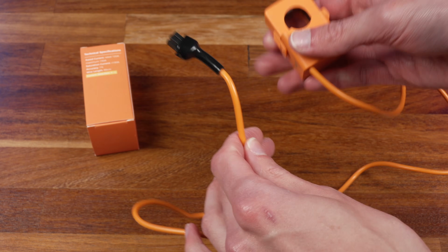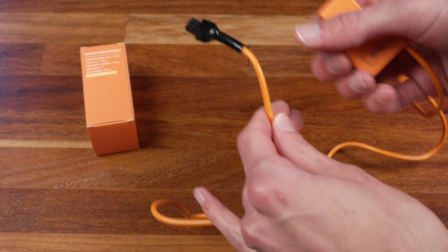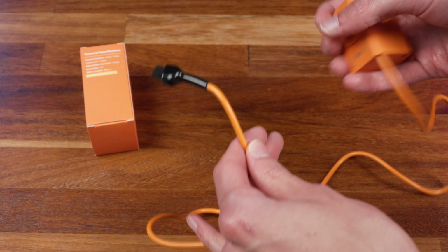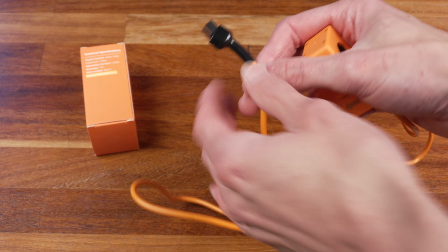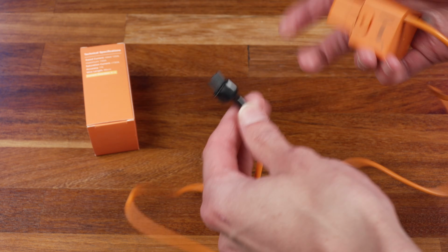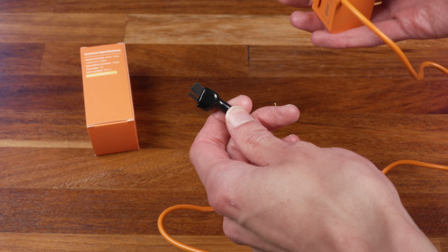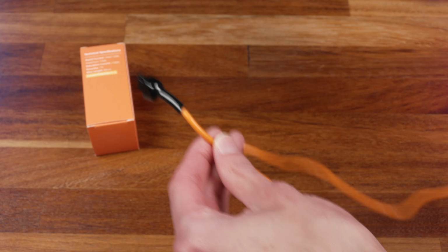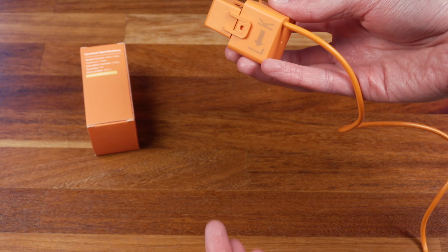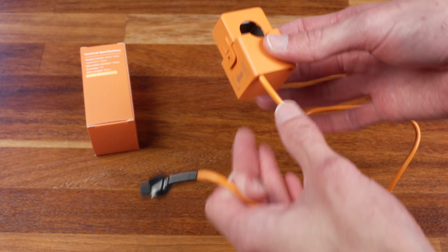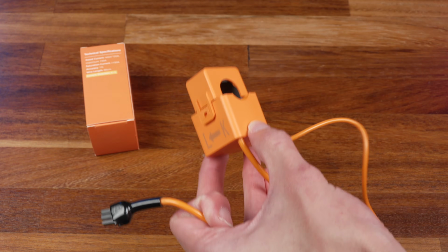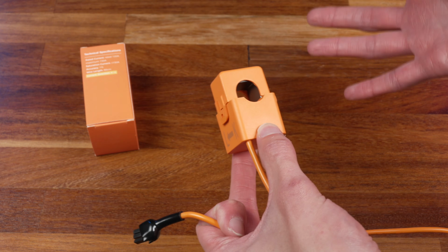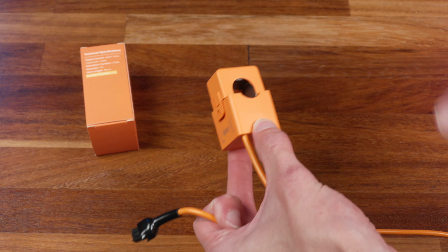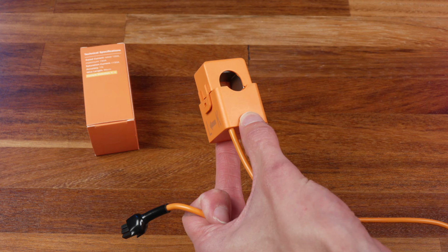So this does mean that it's very easy to install, but it does somewhat mean that you're limited to the CTs that they include, rather than being able to install your own CTs if you prefer. Some other options, sort of products in this market, provide screw terminals rather than these plugs, which means you can kind of swap the CTs out if you wanted to. Realistically, it's not a huge issue though, since these CTs seem to work pretty well, and even though they're rated up to 120 amps, they seem to be completely fine measuring much smaller currents. The only downside is that they are very large compared to much lower rated CTs, so they might be a bit of a squeeze to install into some consumer units.